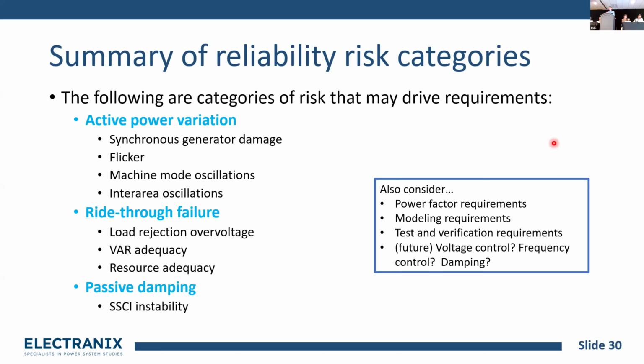We're also worried about ride-through failure, and failure to ride through for these loads. In the past we didn't really talk about load ride-through capability. This is new, but now we're worried about load rejection over voltage, VAR adequacy or voltage control, and resource adequacy, which could include frequency control as well.